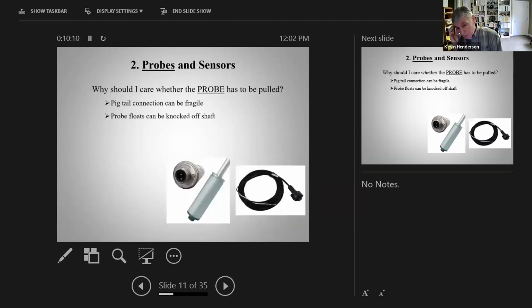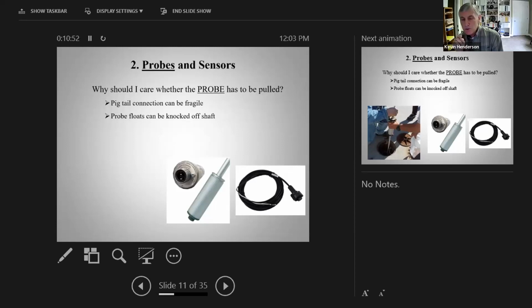So the way that we do that is really pretty simple again, but you do understand that pulling that probe is dangerous. Why? I mention that because any probe that has been inside a tank for a period of time, when you pull that probe out, the only way to get the probe out of the tank typically is to disconnect the wiring. The photo on the far right is a little pigtail that Veeder-Root has to connect the probe to the wire that goes back to the console. And the picture in the center, of course, is the probe itself. And you see the two little pins in the middle there. That's just a plastic housing in there, and those two little pins are in that plastic.